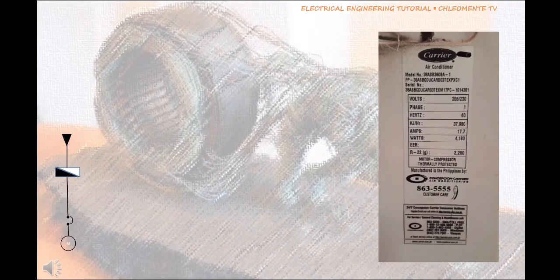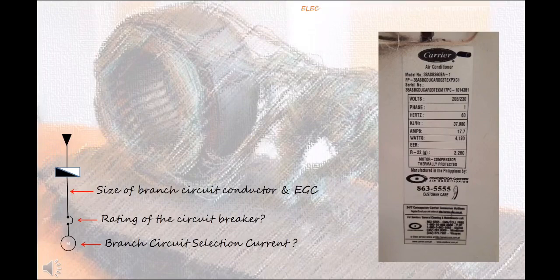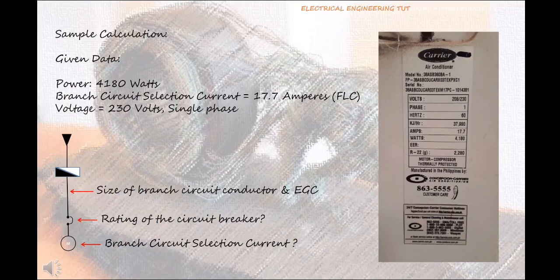In this given air conditioning unit, we will show how branch circuit selection current is determined, how to properly size the rating of the circuit breaker, and how you determine the proper size of the branch circuit conductor and equipment grounding conductor or EGC. Following are the given data: Power rating equals 4180 watts, voltage equals 230 volts single phase, branch circuit selection current equals 17.7 amperes. If this branch circuit selection current of 17.7 amperes is not available or there is no technical data sheet, we can refer to PEC 2017 Table 4.30.14.2 for single phase motor and Table 4.30.14.4 for three phase motor for the entire calculation. Now we can start the calculation.